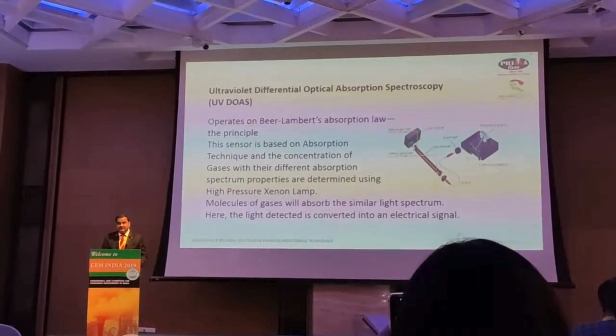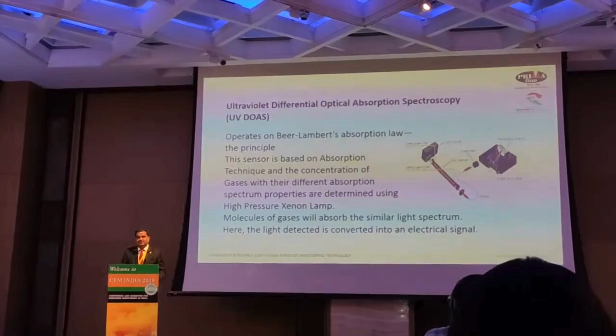The other technology we present is ultraviolet differential optical absorption spectroscopy. The reason we worked on this was that we will be able to get the actual NOx, that is NO plus NO2. So we don't need to use any catalyst or converter technology here. Again, here I'll have some benefits of that. Again, you can have a high measurement range. There is again the flexibility for a low measurement range also. As I mentioned, the NO and NO2 are measured separately here. So in real time, you can have NOx without any catalyst or converter to be used.